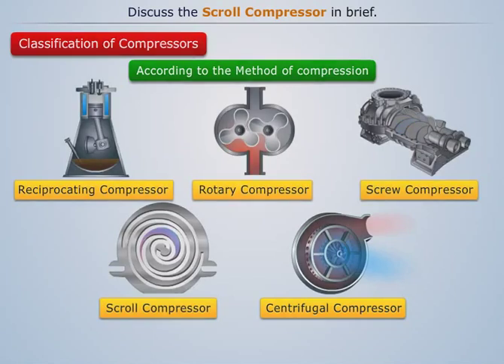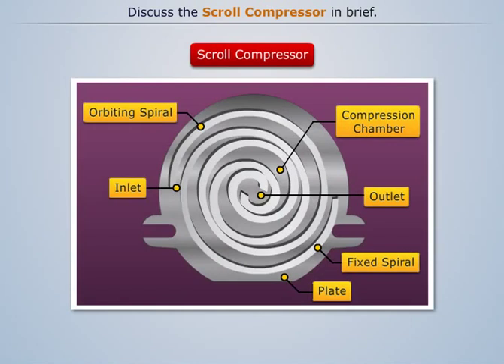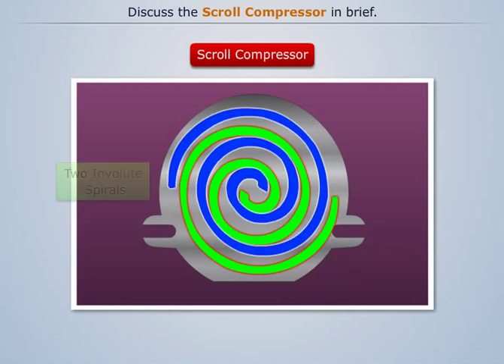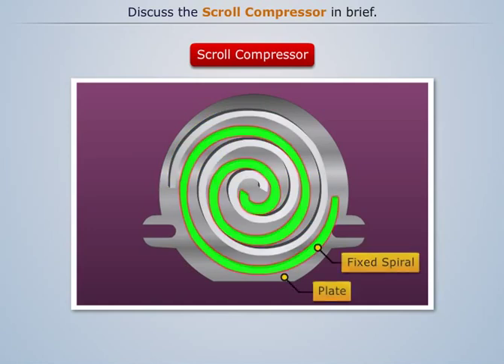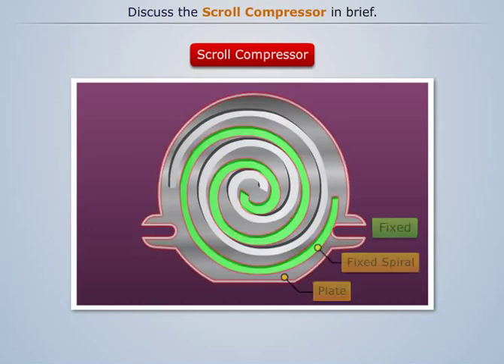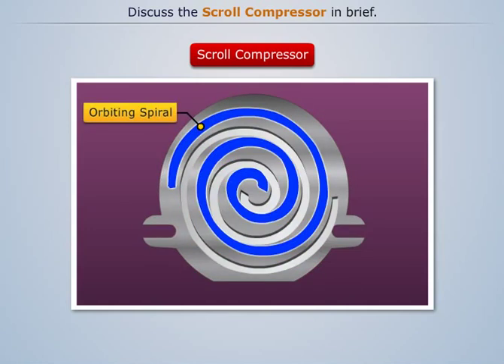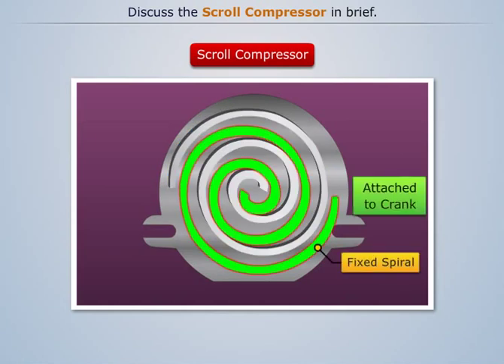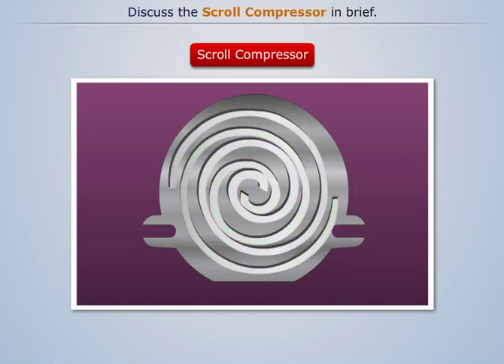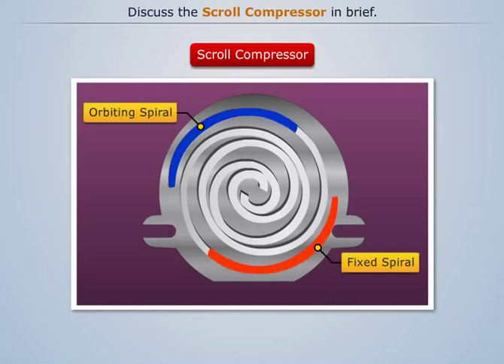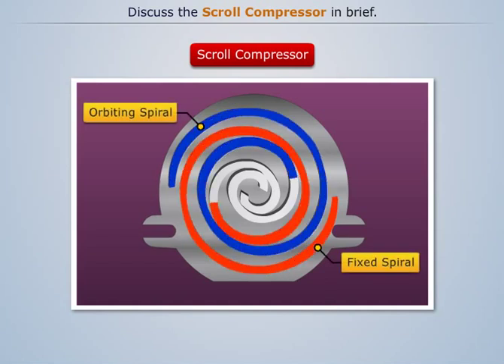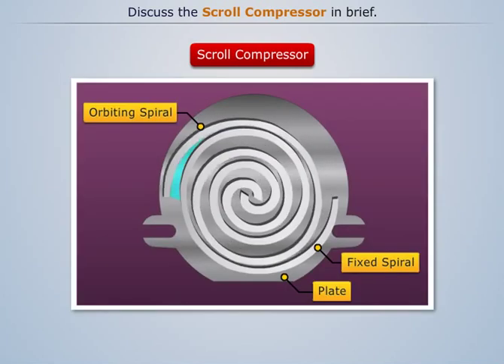A typical scroll compressor consists of two involute spirals. One of them is fixed to the plate, and the other orbits around the fixed spiral. The orbiting spiral is attached to the crank of the compressor. The fixed and the orbiting spiral have geometrically matching surfaces.